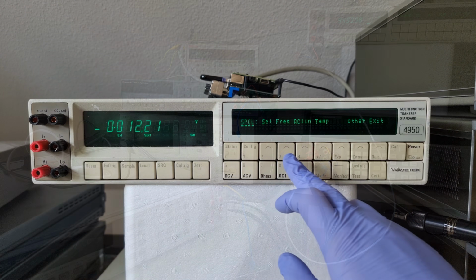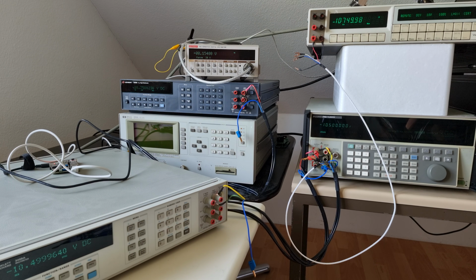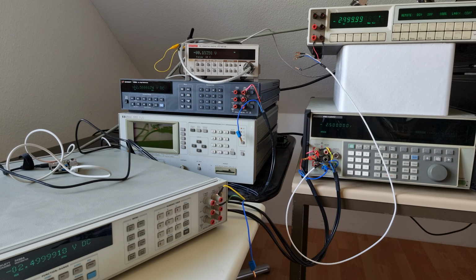I'll have to keep an eye out for a leaked service manual, or I could try the 4920 procedure, which should be similar. Another thing, since we are all gathered here, last time I was under the impression that this meter could only read its points of interest and would refuse everything else. That is its default behavior, but as Tin from XDevs has pointed out in the comments, you can disable it and easily make it act like a normal multimeter. So while DCV linearity is still not its primary purpose, it should have some of it, and so naturally we have to test it. Here I've configured the calibrator to do a -11 to +11 volt sweep in 250 millivolt steps, which are then observed by both 3458As and Datron.